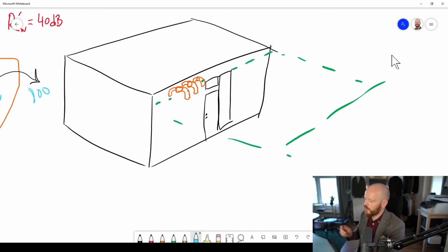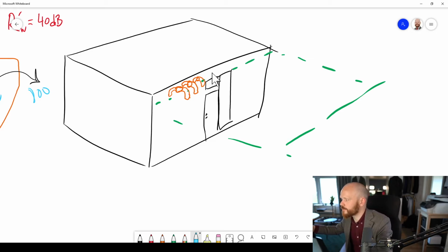And that's what's going to happen if you add too many of these. So remember that if you need many air transfer units, you will need to raise the bar on each of them to compensate, so that they will have to be somewhat or even a lot better than the requirement. If you're aiming at 40, you might need to aim a lot higher with these because you've got so many of them. And you can calculate all of this, of course, but it might be a little acoustical landmine that is easy to forget. So don't miss that one.